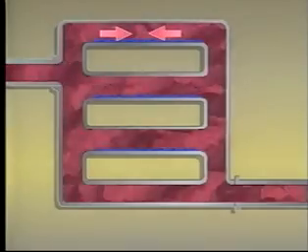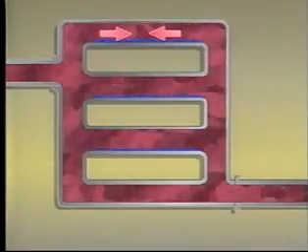Thermal shock can also occur easily in steam coils if they are constructed as shown here. Since the steam is directed toward the center tube first, it can reach the return header before the top and bottom tubes are filled. Consequently, steam feeds the more remote tubes from both ends. With steam flowing into both ends of a tube, waves of condensate flow toward each other. These waves have the potential of trapping pockets of steam between them. If this happens, thermal shock will result when the pocket of steam collapses and water hammer will probably occur.